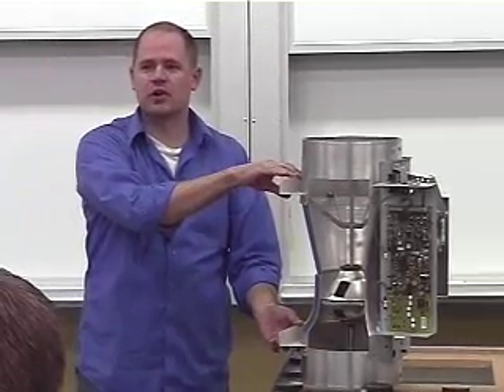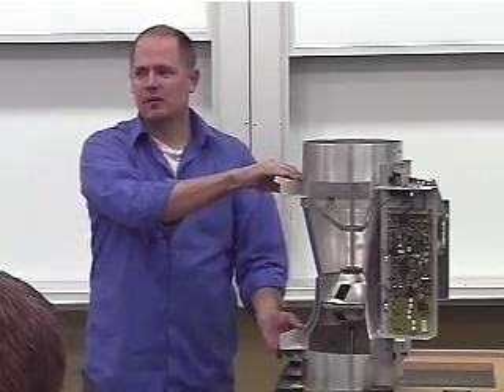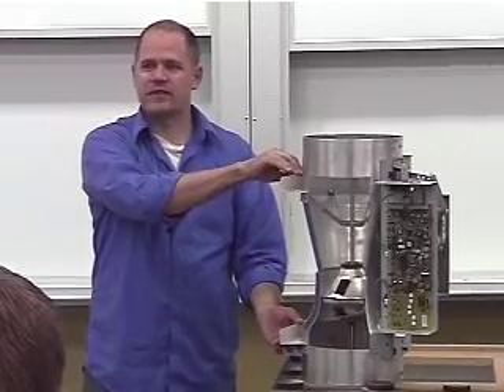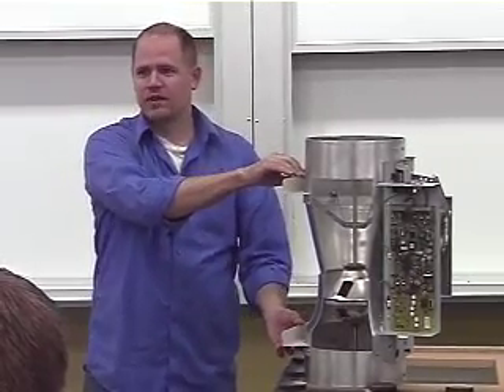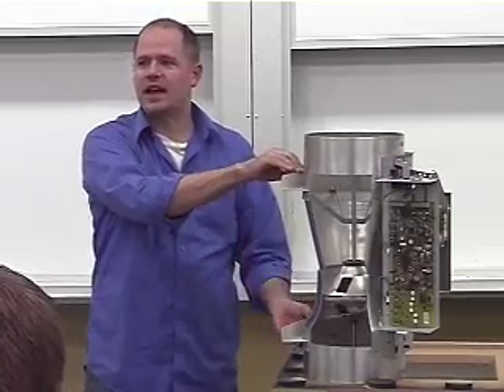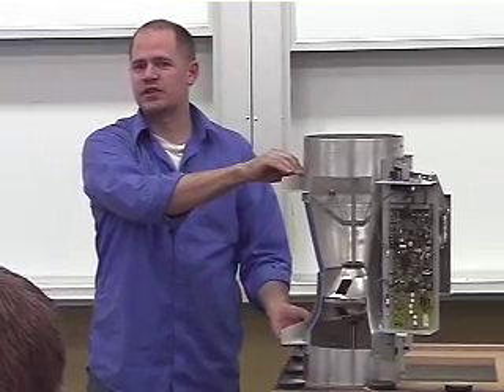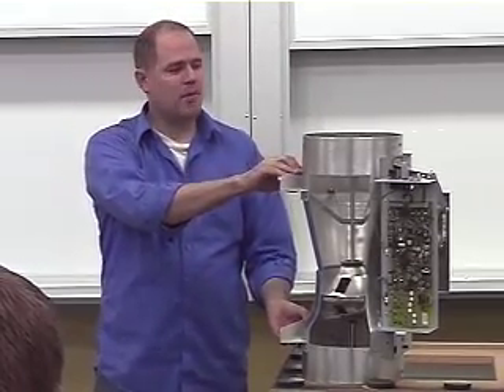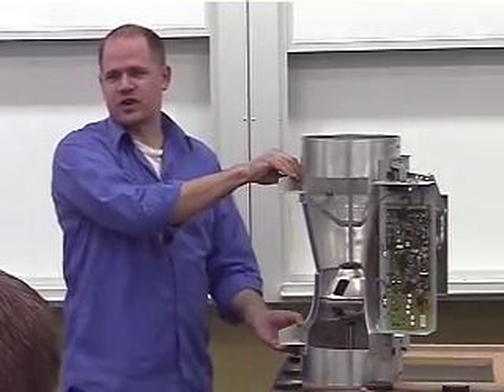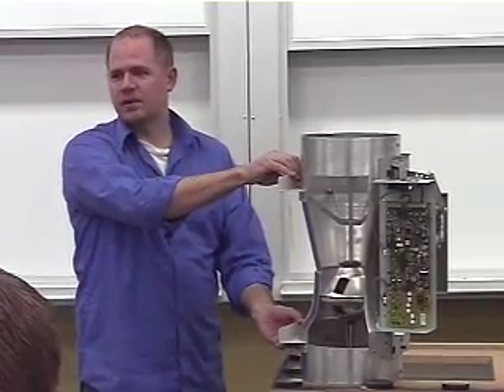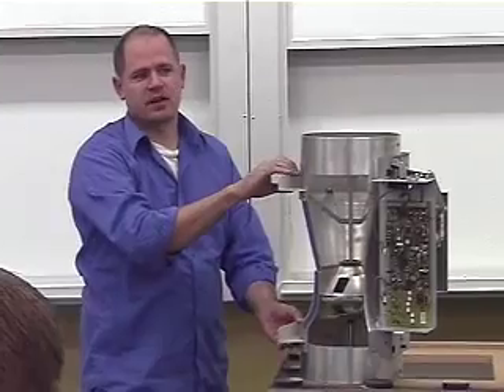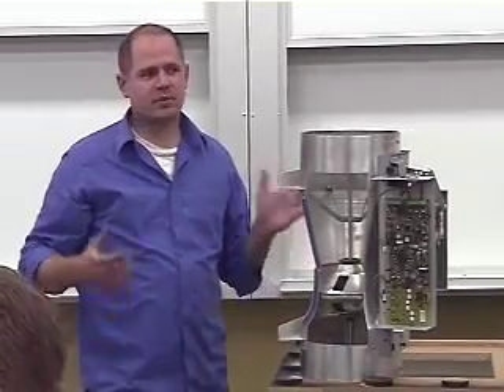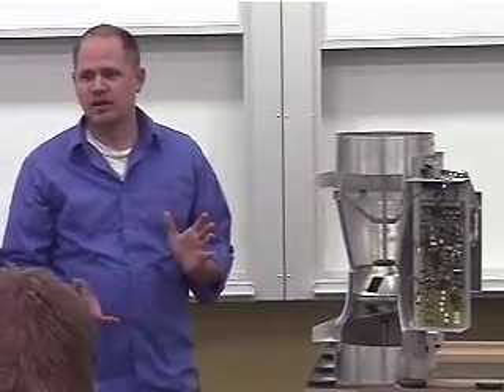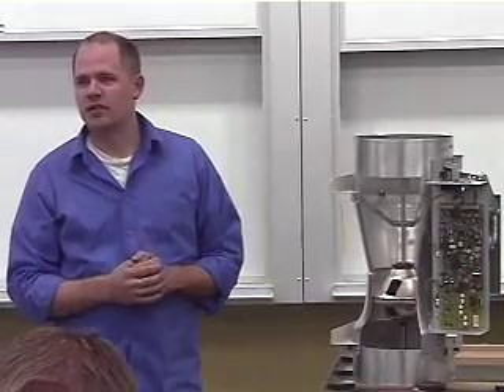It will still attempt to control and do the best it can, but once the physical requirements for the valve aren't met, obviously it's going to say, hey, I can't necessarily guarantee you're getting what you want. And the maximum it goes up to is 3 inches of pressure drop across the valve. Typically your system gets balanced so that it meets those requirements, and as long as you're maintaining your duct static pressure, everything's good across there.